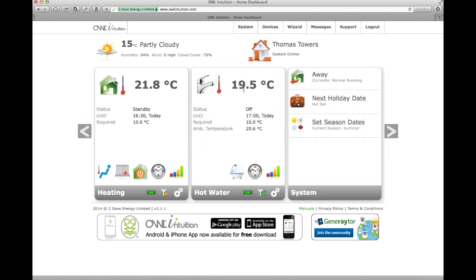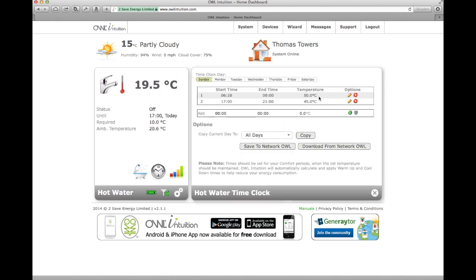The final panel is the hot water. I currently have the sensor in the middle of my tank — we have three thermostatic ports. This allows you, just like the central heating, to control your hot water temperature and save money. Most boilers just have a thermostat set to 60 degrees, heat all the way up, then shut off — you use a lot of gas, and then you mix it with loads of cold water in the shower when you didn't actually need it at 60 degrees. So you could say heat to 50 degrees in the morning when there's high demand, but in the evening throttle back to 45 degrees, which is more than hot enough for a shower, a bath, or washing up.